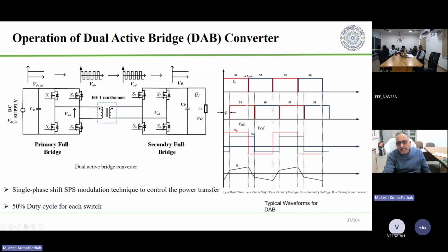The primary thing is that you create a voltage here and here which are phase shifted. So this is the phase shift, and this is the voltage on the primary side and this is the voltage on the secondary side. So if you want to deliver power to the secondary side, this primary voltage should be leading, and this angle of lead will determine how much power is fed to the secondary side.